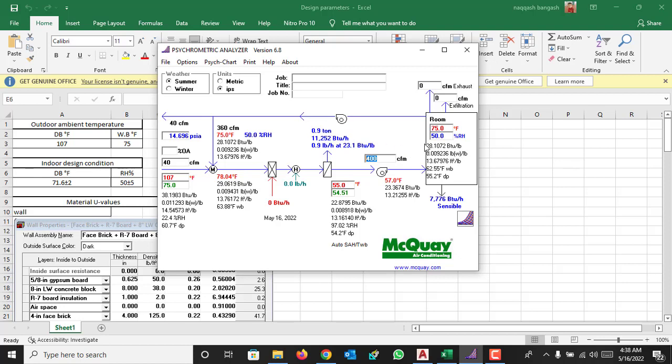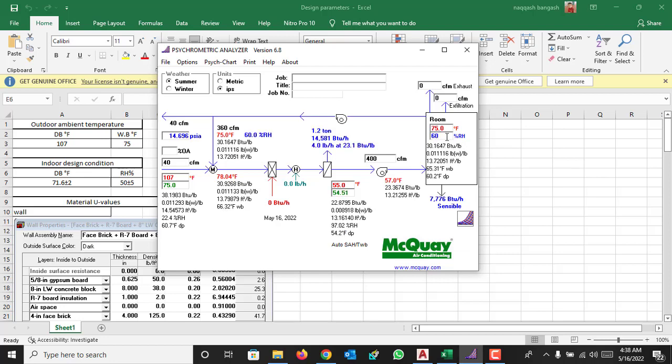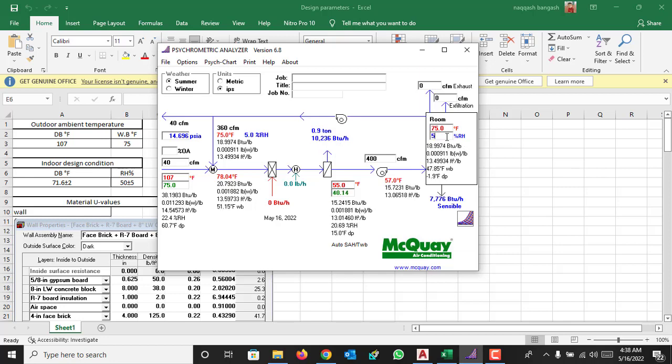And we consider the room temperature is 75 Fahrenheit at 50% relative humidity. If you increase the room relative humidity to 60%, the latent load will increase.